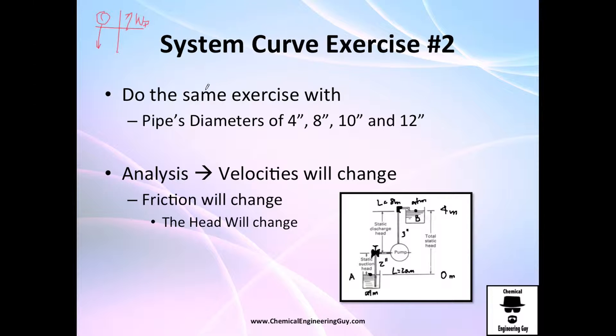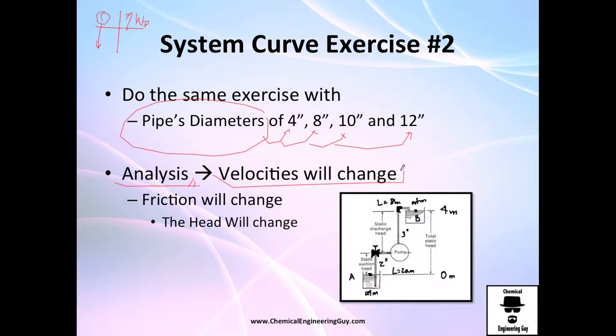In this exercise number two, we're going to check out the difference if we wanted to change the pipe diameters into four, eight, or even greater diameters. The main analysis will be that the velocities will change. Every time you change the diameter, velocity drops by squares. So the velocity will change not only because of the velocity heads, but also because of the friction heads.